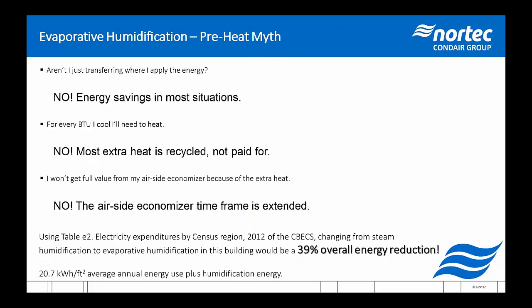And then finally, what about my air side economizer? Well, in reality, we actually extend the amount of time an air side economizer can be used by providing a little bit of extra free cooling in here. Now in this building, and of course I did pick this building to be an absolutely amazing situation for evaporative cooling. However, it can be effective in a whole load range of other situations.